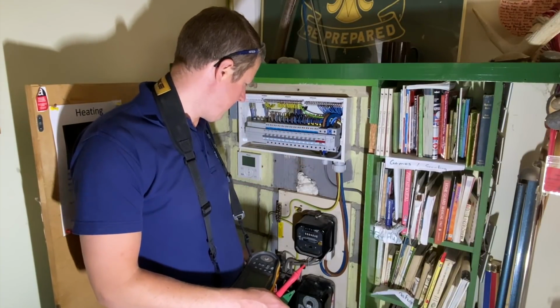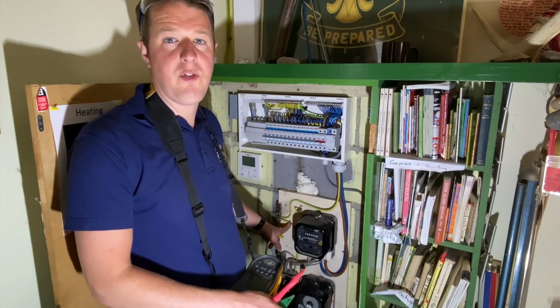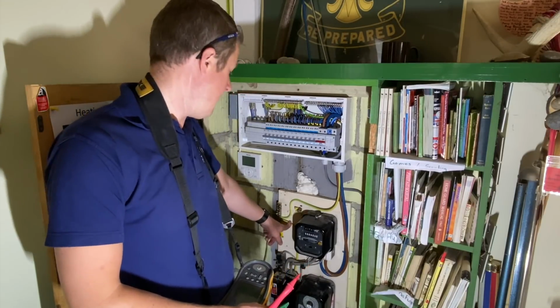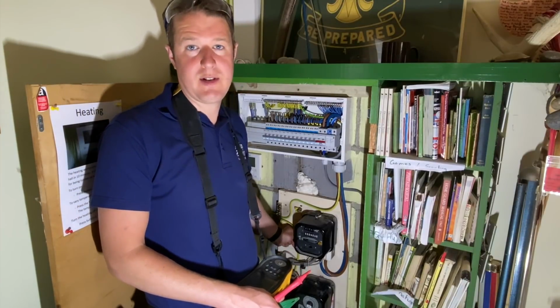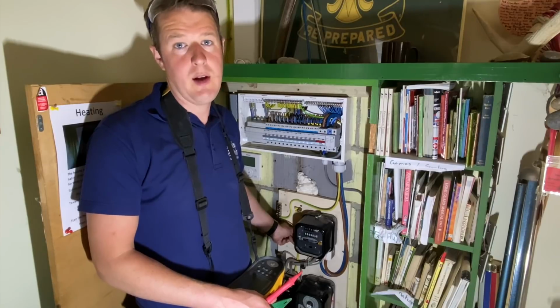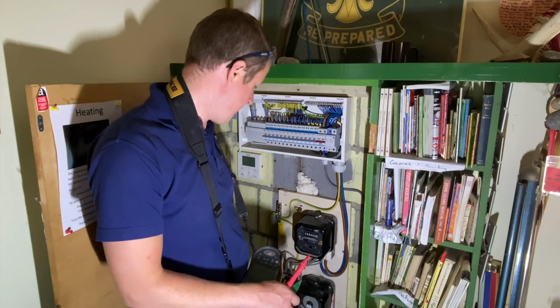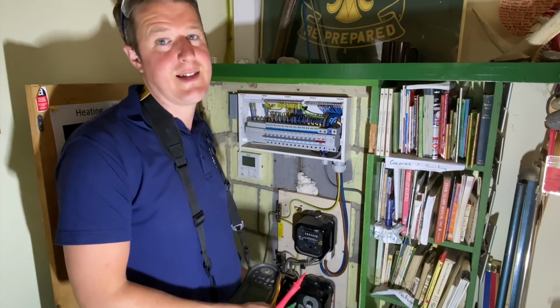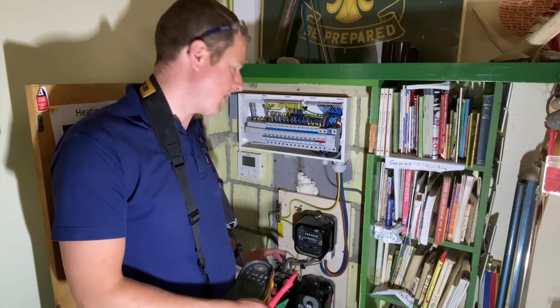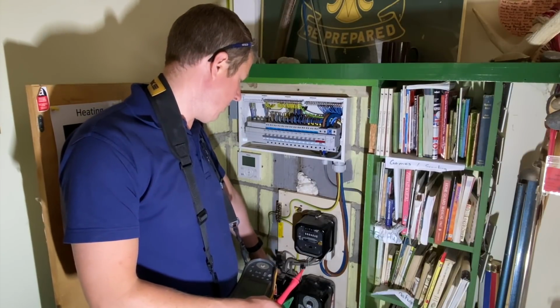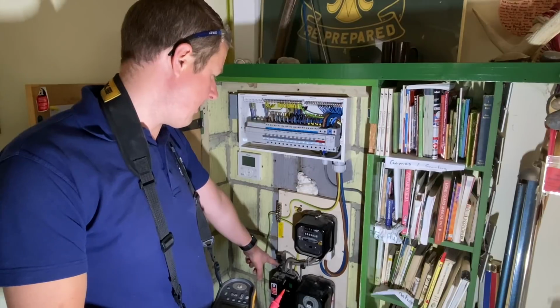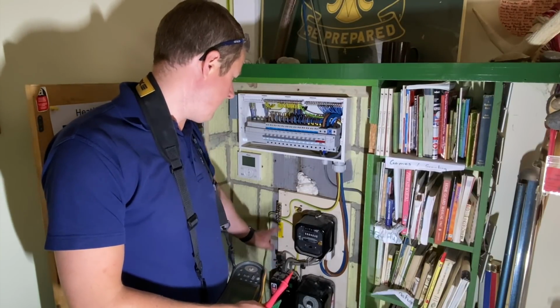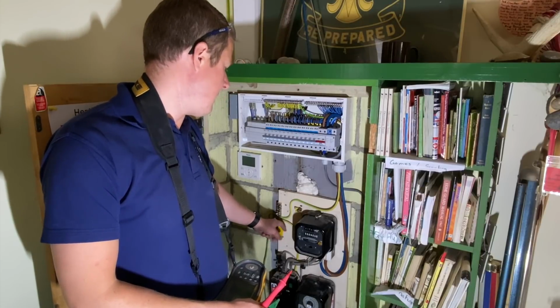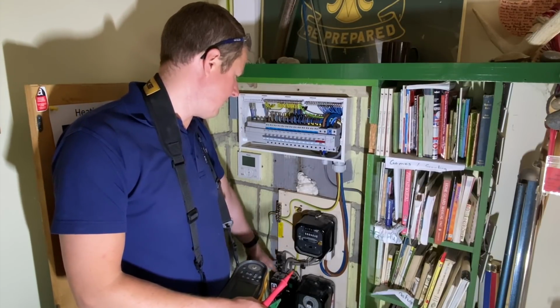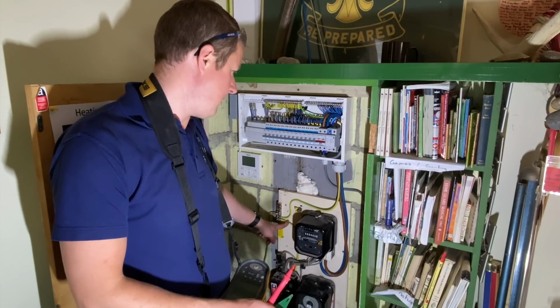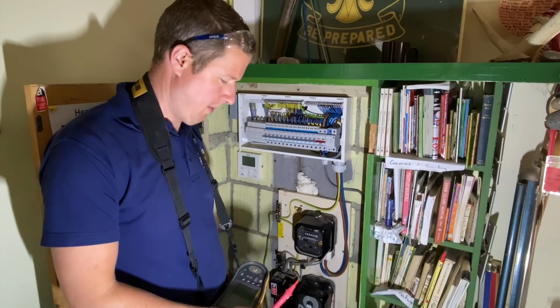I'm going to start off by doing an external earth fault loop impedance test, or Ze. This is to basically measure the resistance of the external earth fault loop path to make sure that there's a good earth for the property, etc. So this is what we call a PME supply, or TN-C-S, which means that the supplier's earth is combined with the neutral at the supplier's neutral block here, which you can see the neutral and the earth come both out of the same terminal. This is the main earth terminal, and what we're going to do is disconnect the main earth conductor from the supplier's PME terminal, and then we're going to use that to test between there and the incoming live at the consumer unit.